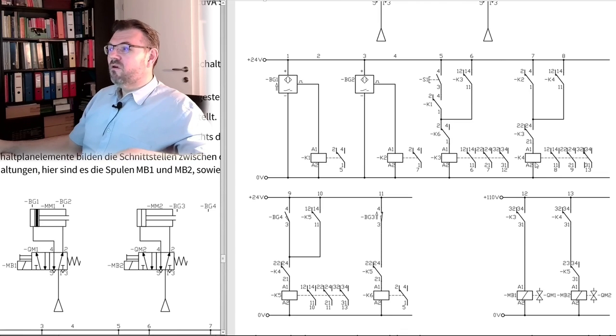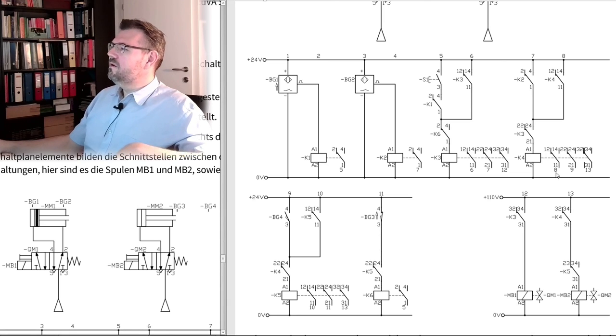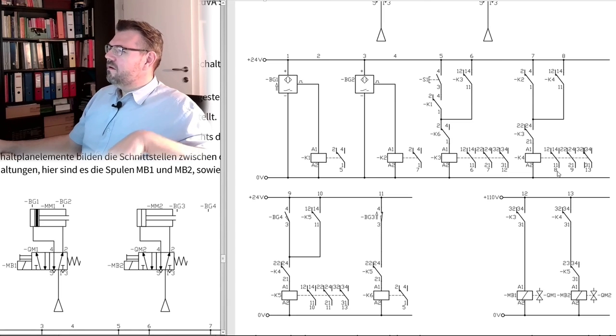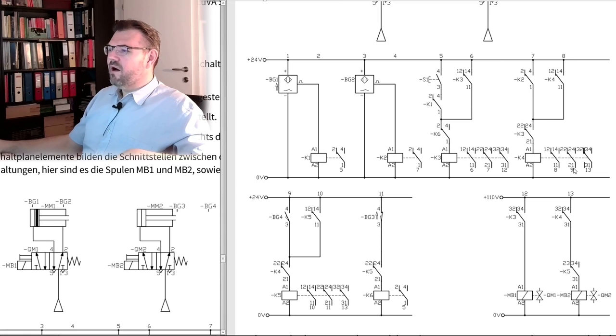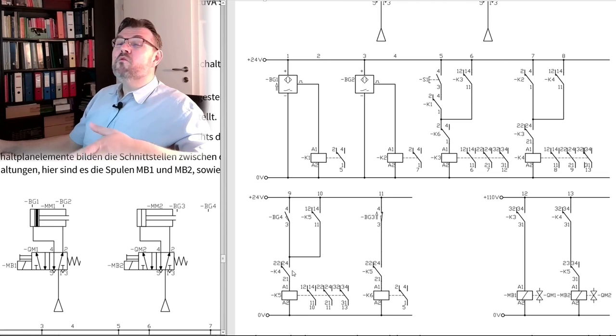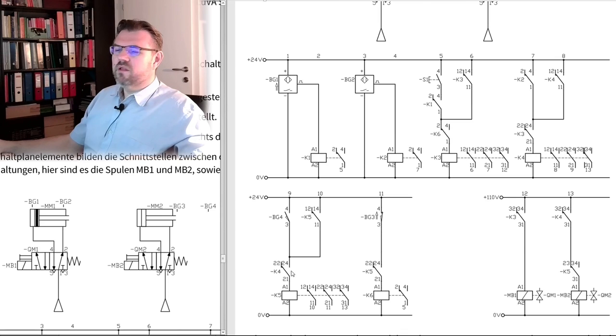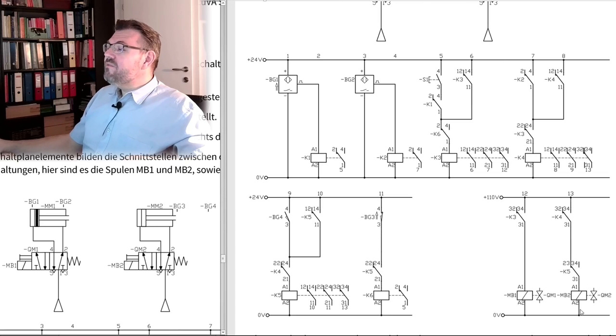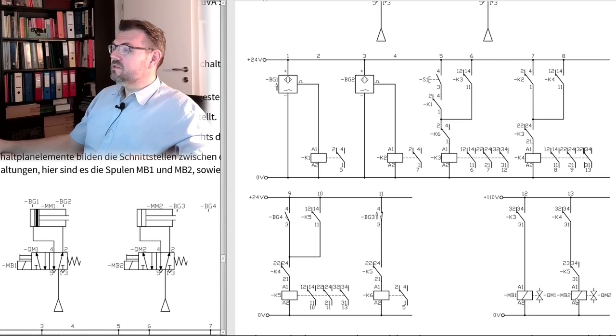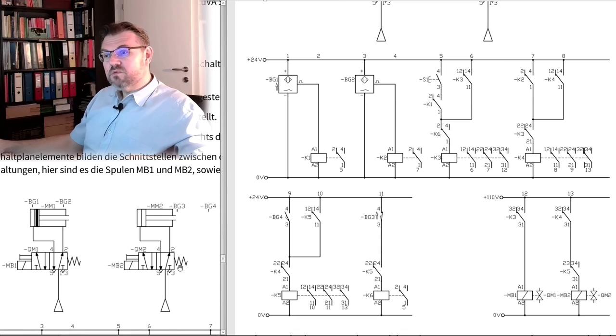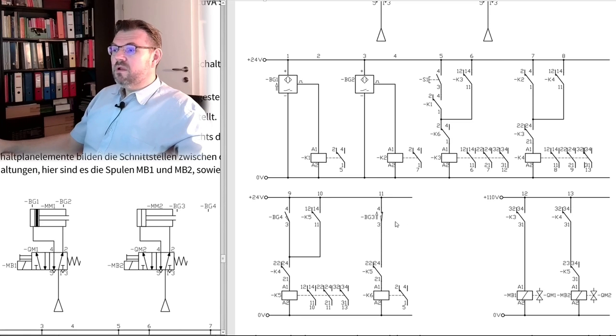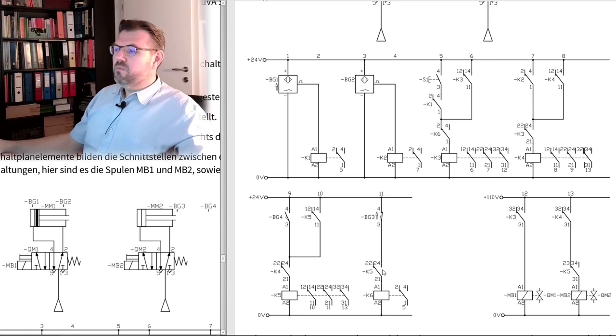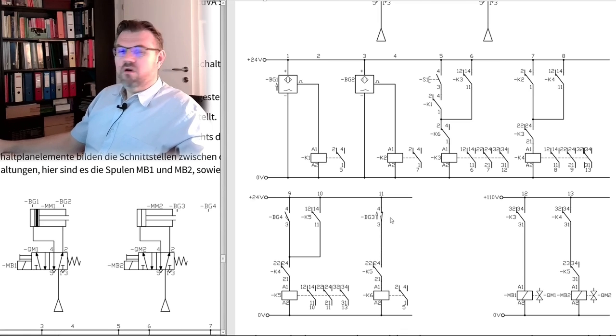What is K4 doing? In path number 8, it is storing, it is holding itself. In path number 9, here, this we know, this is probably again some preparation of the next step. Close here, but right now it has no effect. And here K4, close, activating MB2. So MB2 is activated, switching QM2, QM2 is switched, so BG3 will be released, here it is open, does not really matter, because K5 was also open, but okay, will be turned off.